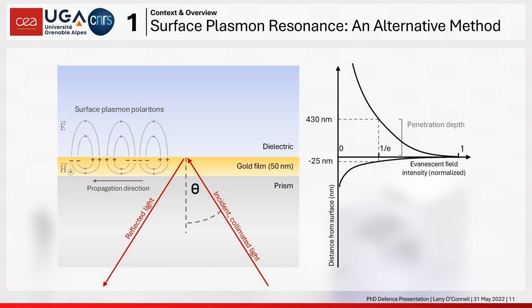This allows you to transduce physical phenomena — changes in mass or refractive index at the surface — into an optical signal. To illustrate: on a small section of a biosensor surface, we've immobilized two kinds of antibodies — Antibody A specific to Bacteria A, and Antibody B specific to Bacteria B — plus a control region. We choose a single observation angle and bounce light off the underside of the metal-dielectric boundary. At a given observation angle, we have a reflectance value that depends on the refractive index above the surface.